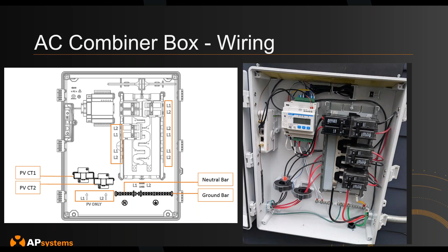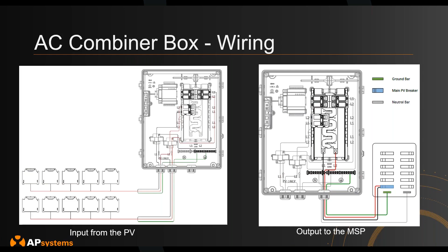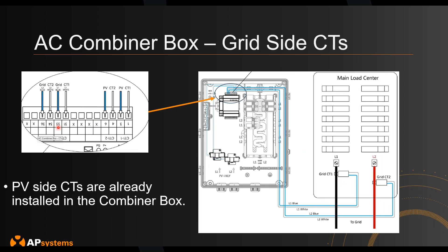One other thing, this is what it looks like as well. Strings go in here, shown over here, and the CTs basically connect to the main service panel onto a breaker here. This is also where the CTs are going to lie. You don't need to do the wiring for the PV CTs because they're already pre-configured, but you will need to do it for the grid side.